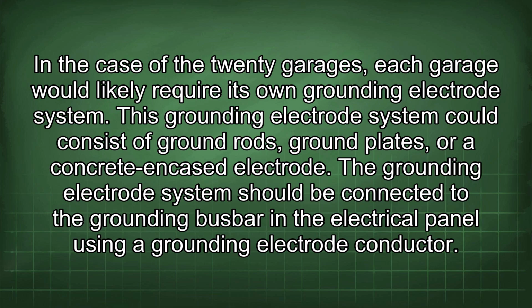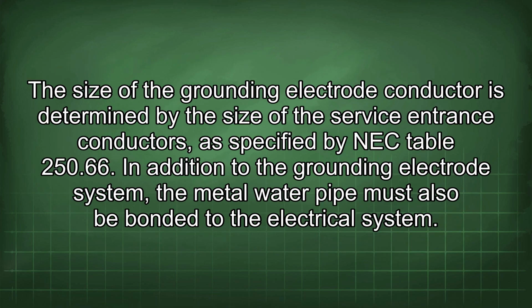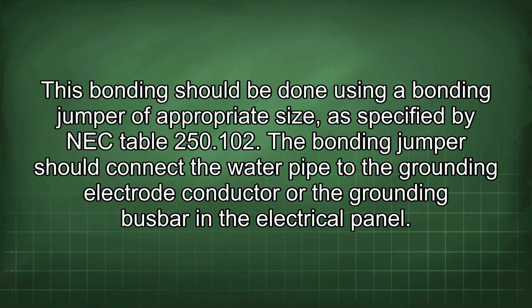The grounding electrode system should be connected to the grounding busbar in the electrical panel using a grounding electrode conductor. The size of the grounding electrode conductor is determined by the size of the service entrance conductors, as specified by NEC Table 250.66. In addition to the grounding electrode system, a metal water pipe must also be bonded to the electrical system. This bonding should be done using a bonding jumper of appropriate size, as specified by NEC Table 250.102.